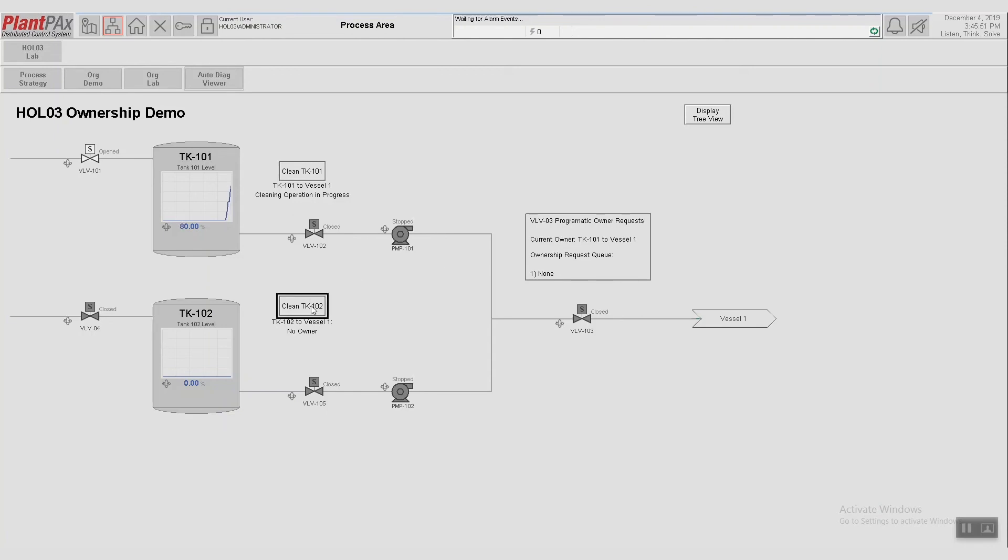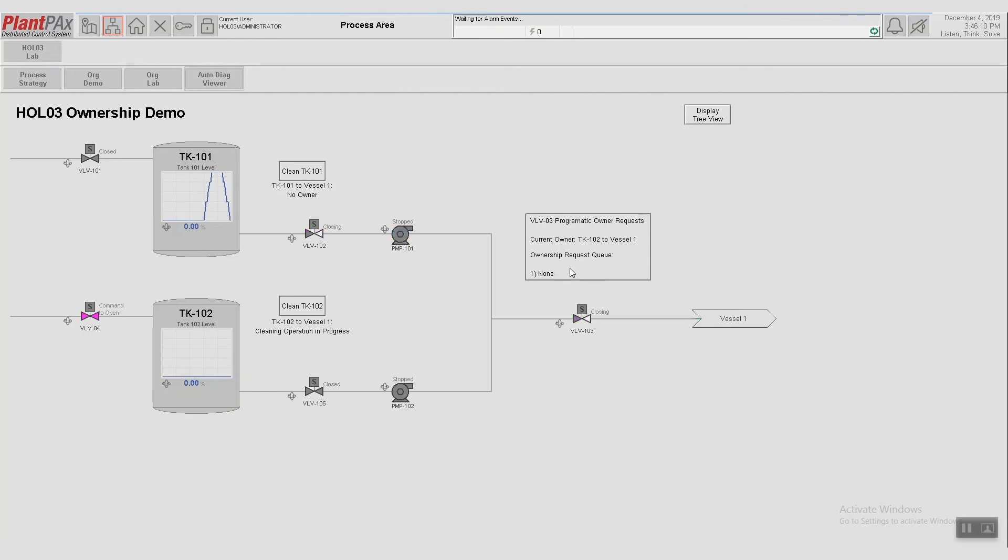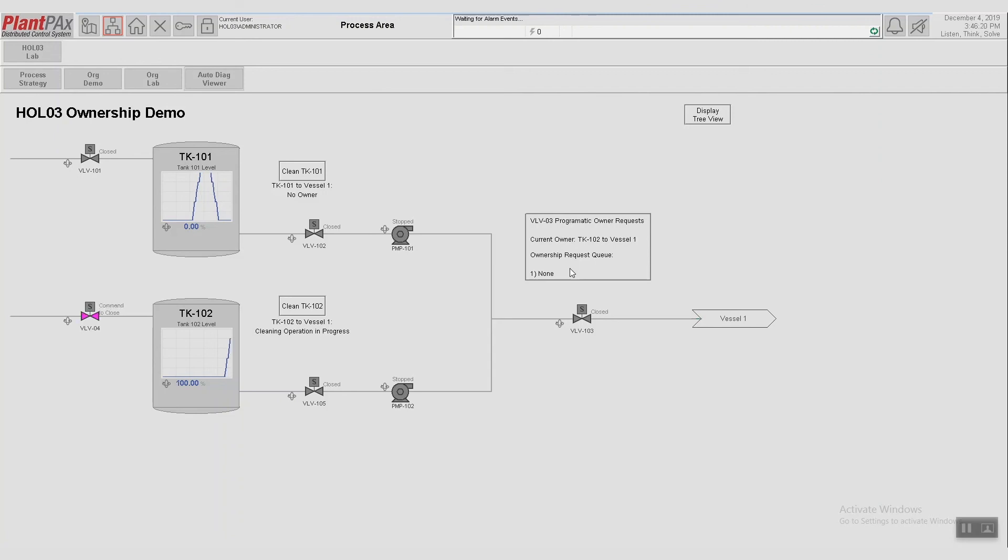Now say I want to clean Tank 102. If I request that operation to start, it doesn't allow the operation to start until that valve frees up. So right now you can see that Tank 101 owns that shared valve, but Tank 102 is waiting in line to own that valve. So now that Tank 101 is releasing it, when it releases, then Tank 102 automatically goes into its operation for cleaning because it was queued.